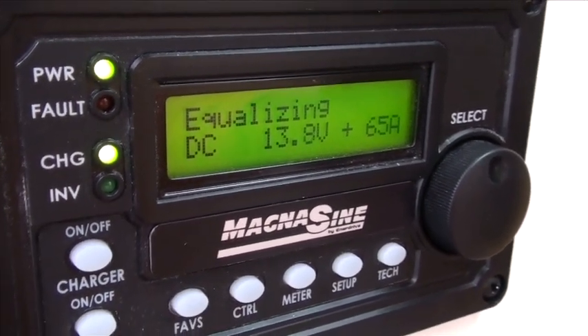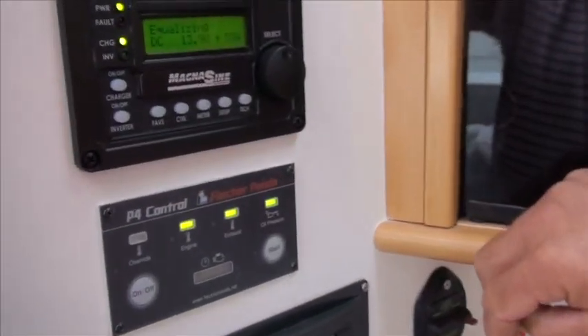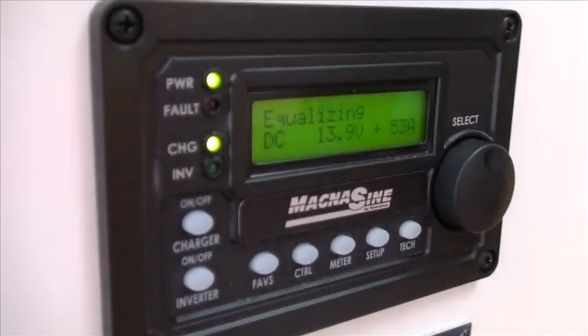And what the possible advantage of doing that is what? The advantage of doing that is you're not drawing so much AC input, so you can use that available genset power elsewhere. So if you wanted to run your aircon and you found that you were overloading the genset a bit, you can wind back the charging. The lithium batteries will take as much charge as you can throw at them up until the point where they're fully charged. Okay, let's put that back.